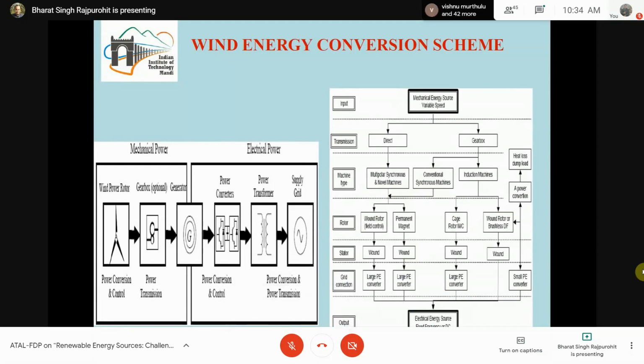Mostly the induction generators used for wind energy conversion systems are rated at a few hundred volts. The supply grid generally available to wind farms is either 11 kV or 33 kV. So transformers from a few hundred volts to 11 kV or 33 kV are required. Sometimes each wind tower has a small transformer stepping up from 590 volts to 11 kV. The whole wind farm works at 11 kV, and then 11 kV to 33 kV, 66 kV or 132 kV transformers are also available, which transform the overall power to a higher voltage level to be connected to the grid. So there are many such configurations, depending on the availability of the electric grid.